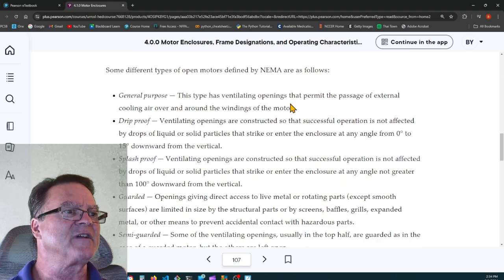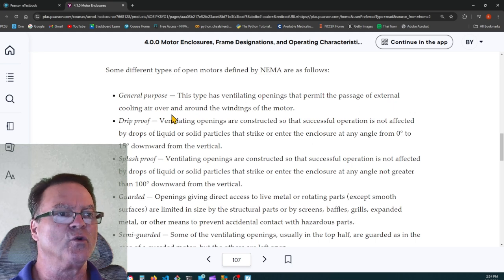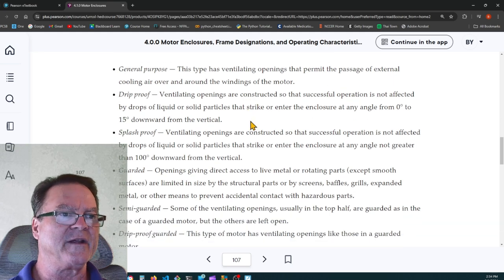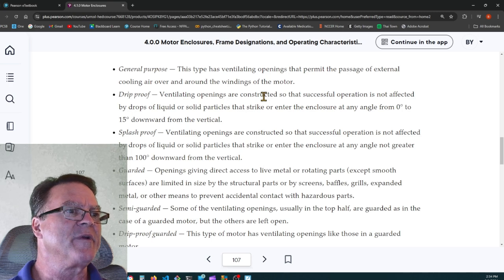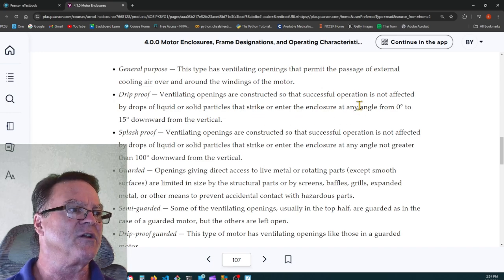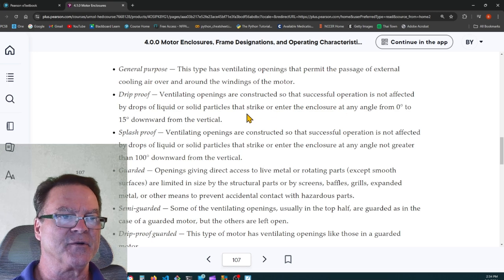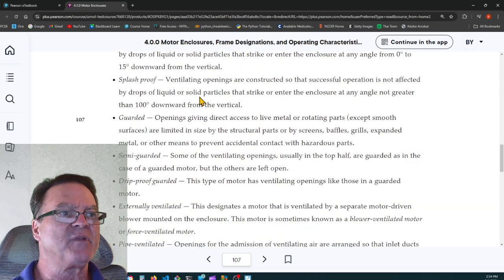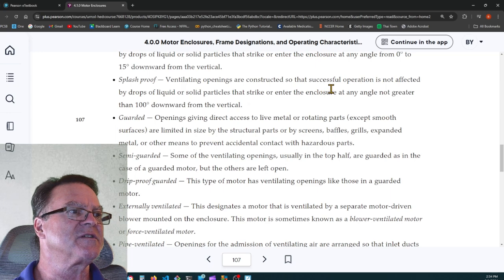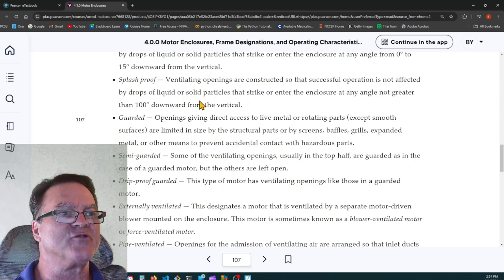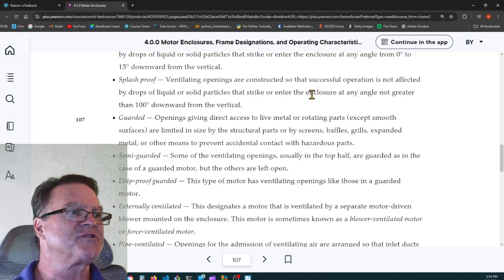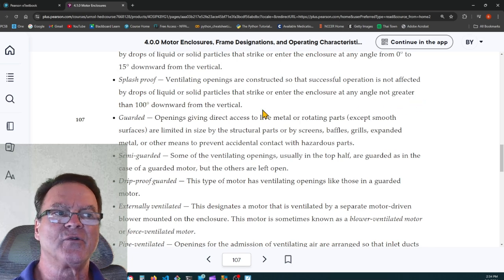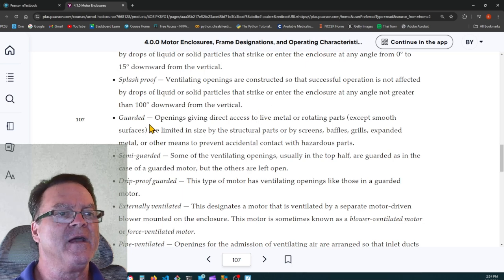General purpose, this type has ventilating openings that permit the passage of external cooling air over and around the windings. Drip proof, its ventilating openings are constructed so that successful operation is not affected by drops of liquid or solid particles that strike or enter the enclosure at any angle from 0 degrees down to 15 degrees. Splash proof, ventilating openings are constructed so that successful operation is not affected by drops of liquid or solid particles that strike or enter the enclosure at any angle not greater than 100 degrees downward from the vertical.